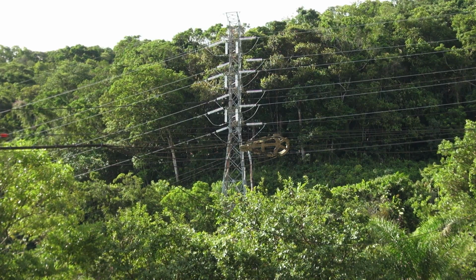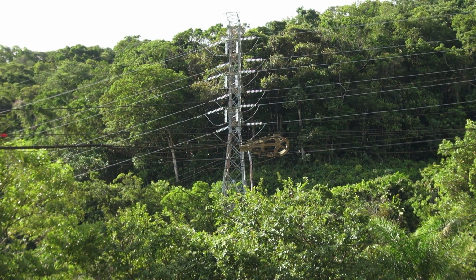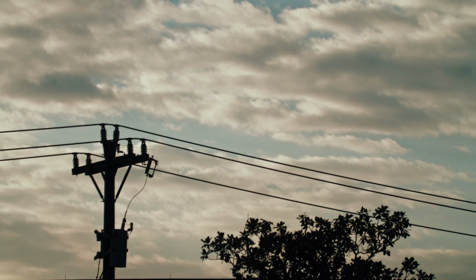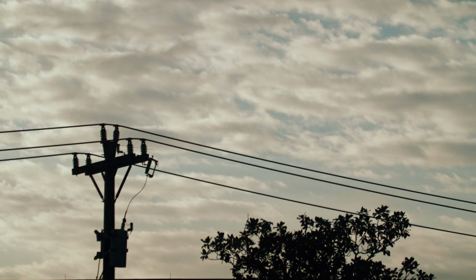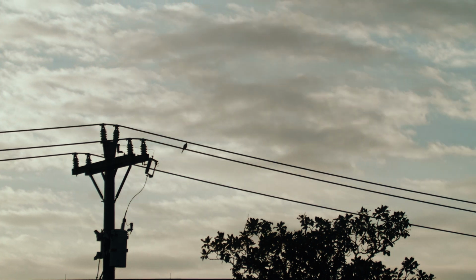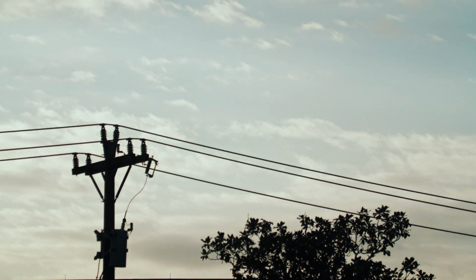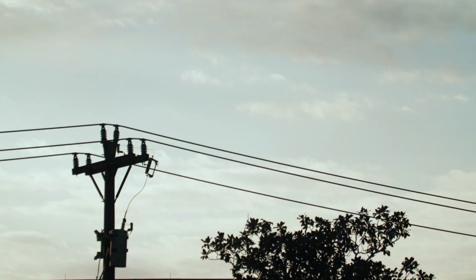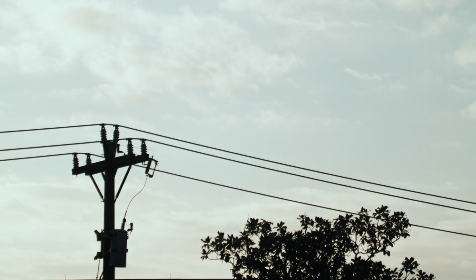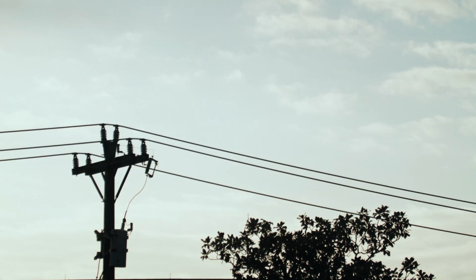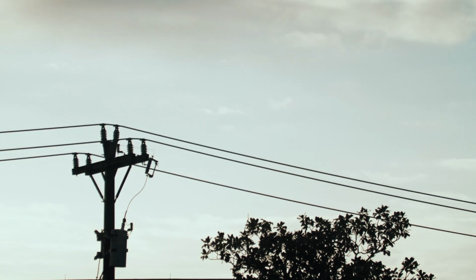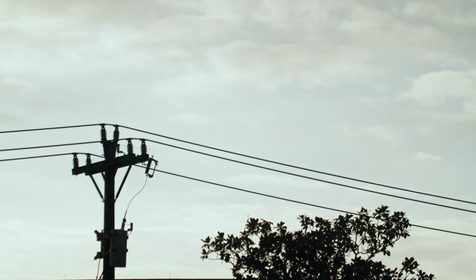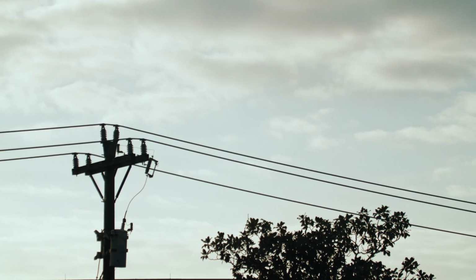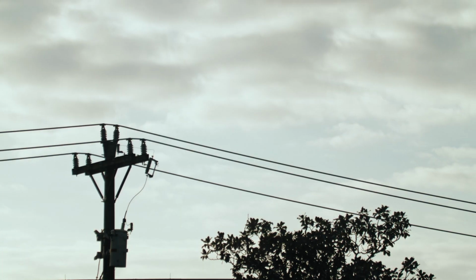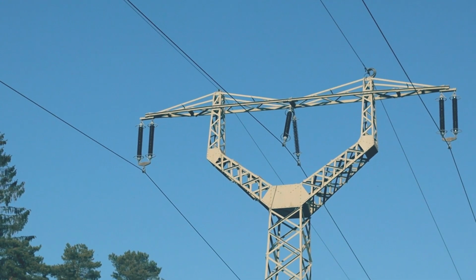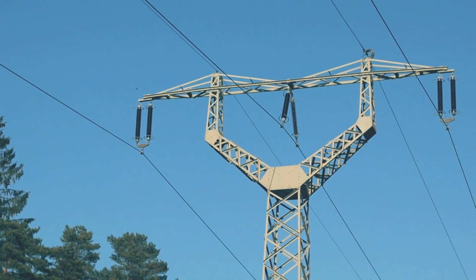When a circuit breaker opens, an electric arc can form between its contacts. This arc must be extinguished quickly to avoid equipment damage and ensure worker safety. For lower voltages, breakers may operate in vacuum chambers. For higher voltages, they are often submerged in insulating oil or use dense dielectric gas to suppress the arc. Modern substations also use protection relays. These electronic devices constantly monitor voltage and current levels throughout the system. If abnormal conditions are detected, the relays automatically send signals to open circuit breakers and isolate the faulted section.